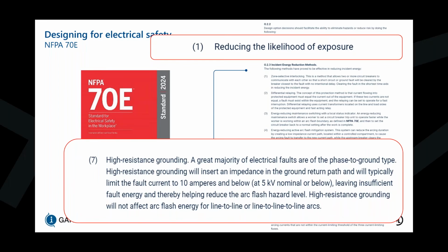All the other incident energy reduction methods are acting after the fact that the arc is already in the system and it's looking to reduce the magnitude. So this could be like zone selective interlocking, differential relaying, arc flash mitigation systems with fiber optic sensors. But with high resistance grounding, we're taking care of 95% of the cases being phase to ground failures, which will limit fault current to 10 amps or less on a system that's 5 kV or less, and leave insufficient fault energy and thereby help reduce the arc flash hazard level.